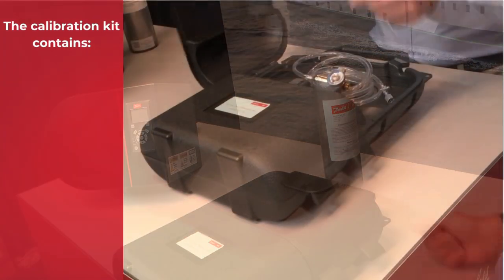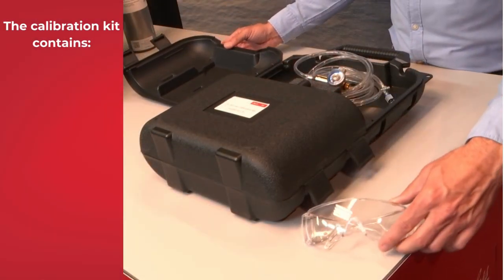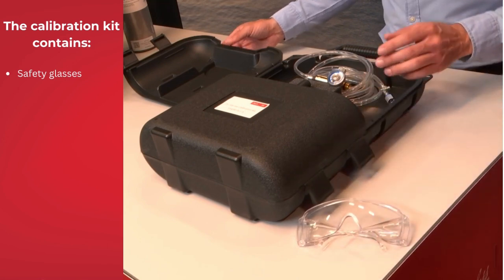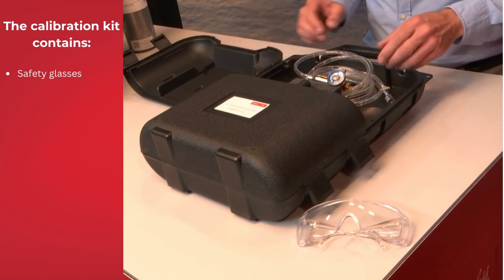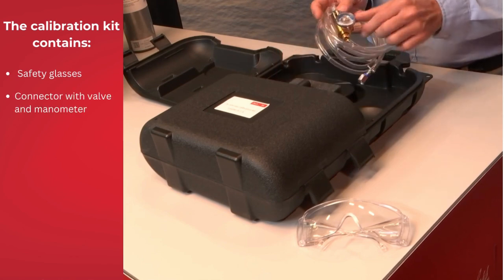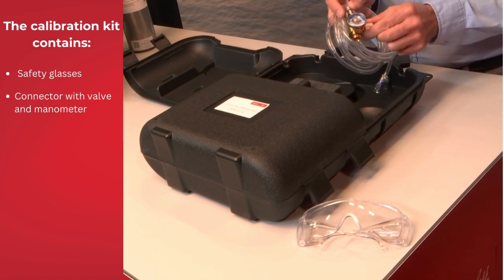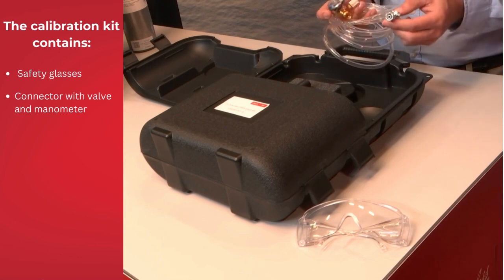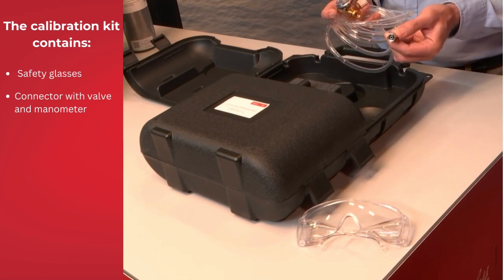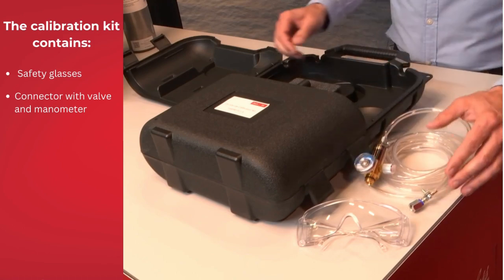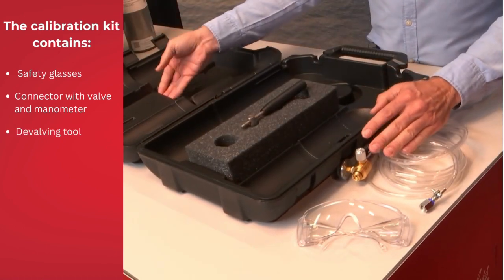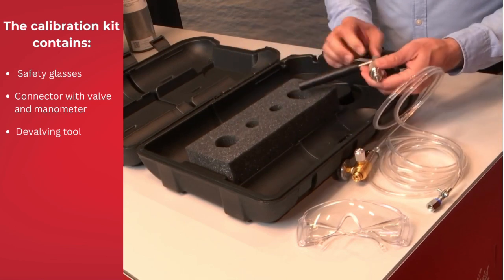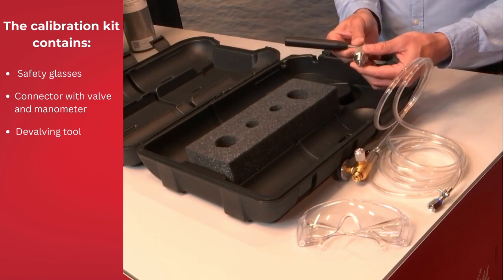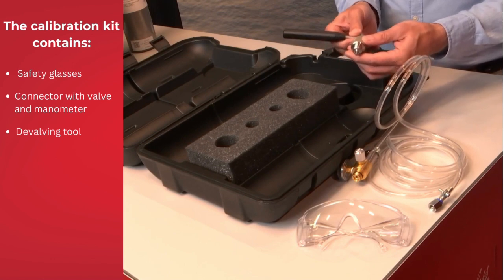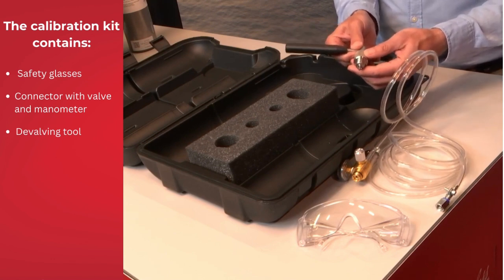Here's the calibration kit. It contains safety glasses that should be worn when operating this calibration kit and the span gas, connected to the span gas bottle with a valve and a manometer, hose and end fittings to connect to the sensor or analyzer. And finally, it contains a devalving tool for the span gas bottle so you can press in the valve and the bottle can be scrapped as normal scrap metal.